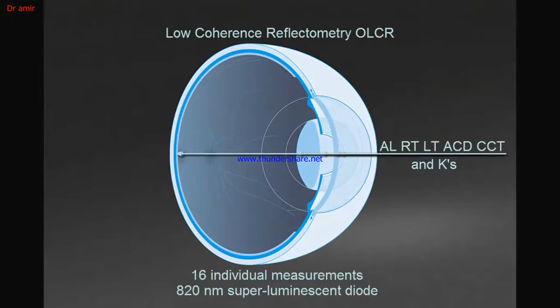EyeSuite Biometry allows the user to adjust the keratometry to either plus or minus cylinders, as well as diopter or millimeter increments. In addition, the user is also able to adjust the keratometric index of refraction. The standard US index of refraction is 1.3375 and the standard European index of refraction is 1.332. These values can be adjusted to ensure that the physician's current personalized optical biometry A constants can be utilized with the Lenstar. It is also possible to specify how the visual acuity of a patient will be entered and displayed. The following options are available: decimal scale, logMAR, Snellen 6 meters and Snellen 20 feet.